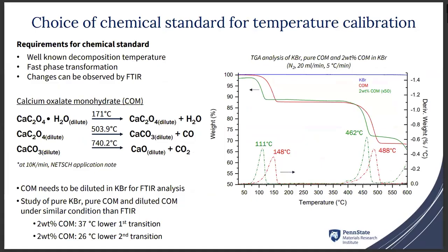So in order to study that, we decided to use a commonly used standard for the thermogravimetric analysis. The choice of this standard is because it has a well-known decomposition temperature, it has a fast phase transformation, and the change can be observed using FTIR. So the compound we decided to use is calcium oxalate monohydrate that leads to a dehydration at around 171 degrees Celsius, then decomposition to form calcium carbonate at 500 degrees Celsius, and complete decomposition at 740 degrees Celsius. So the first 2 events are of interest for analysis because they span within the range of temperature our cell is capable of doing.